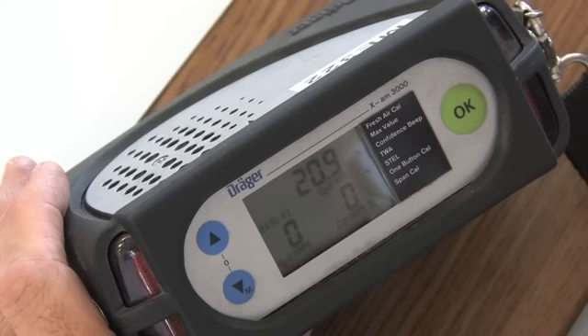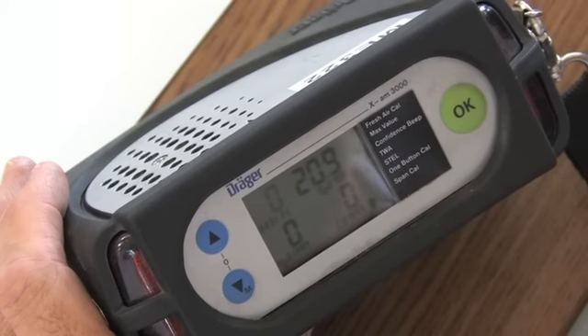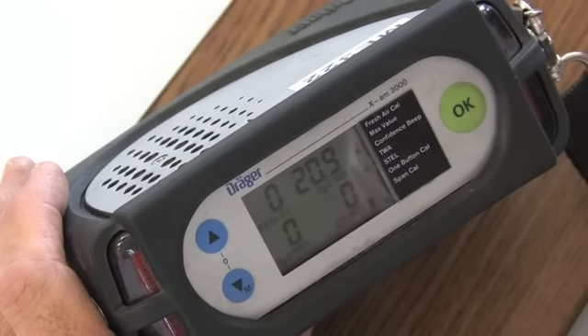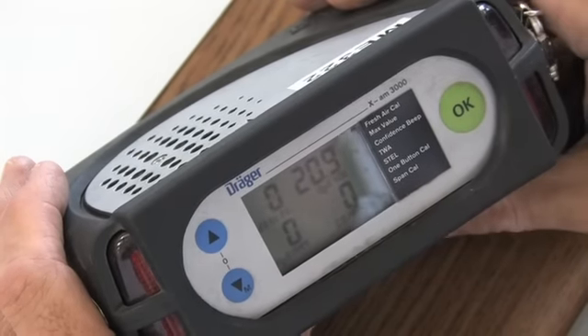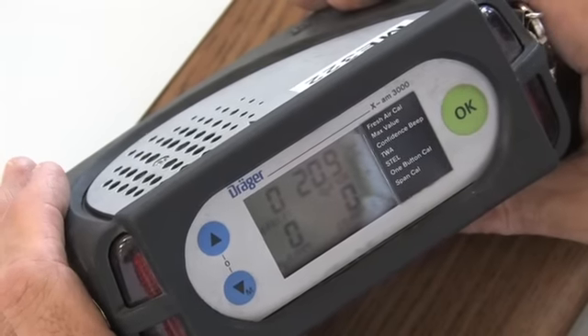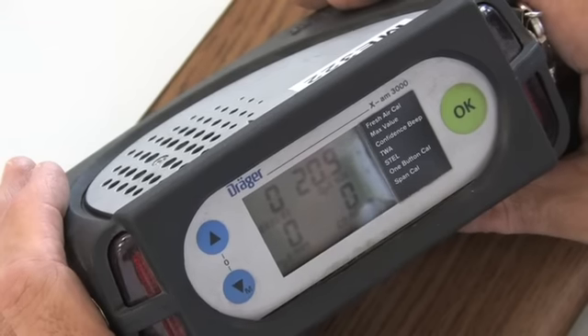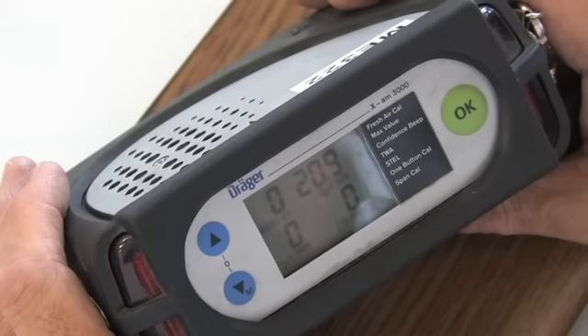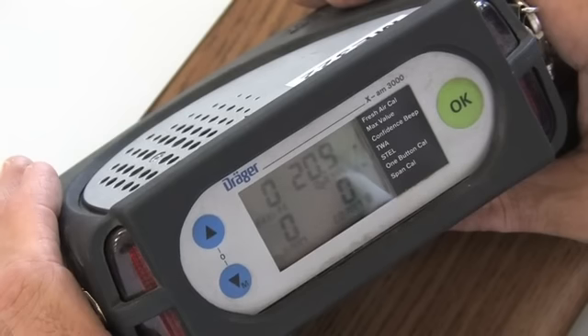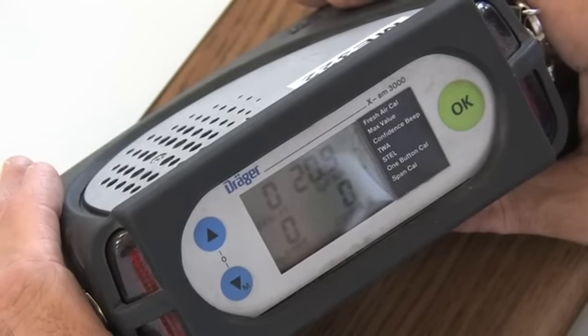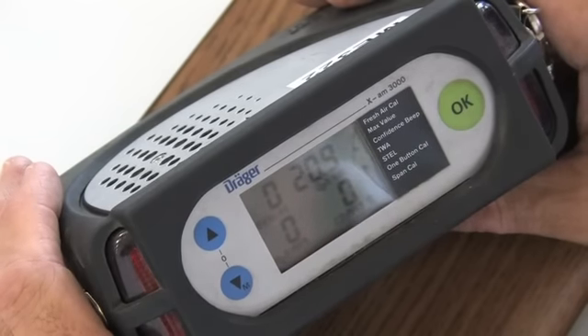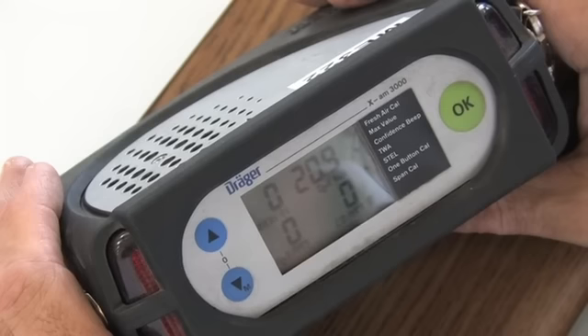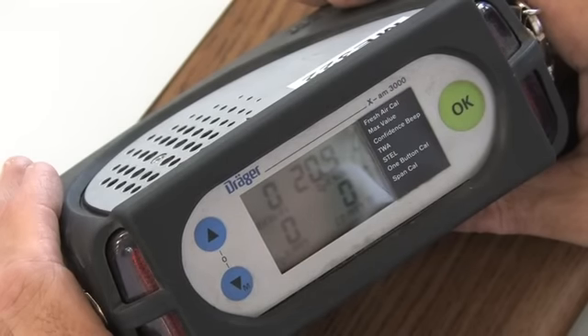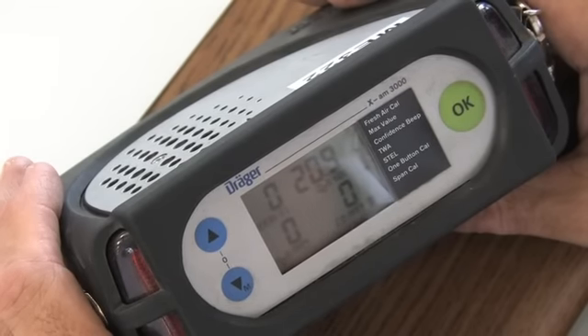You'll also see that the readout on this meter compared to the MiniWarn Draeger and the MultiWarn II Draeger is a little bit different. Instead of it being stacked top to bottom, it's left to right, both on top and bottom. So on the top left, you've got your EX percentage LEL. Now that's different from your Draeger MiniWarn, MultiWarn. This does not read CH4, it just reads EX, EX for explosives.